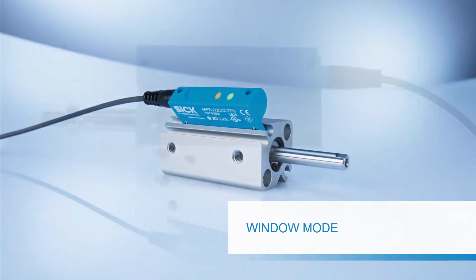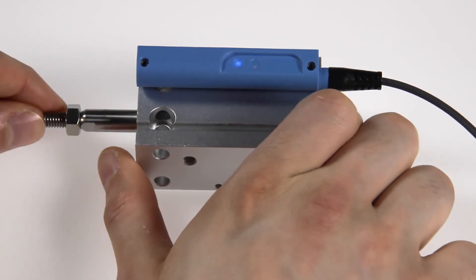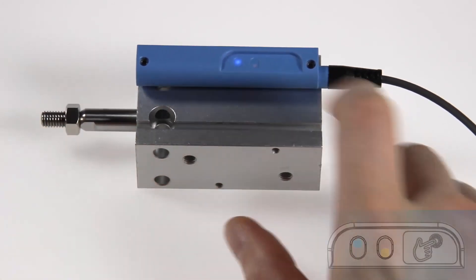Window mode. When using the window mode, a window between an upper and a lower threshold is defined. The switching output is active when the piston is located between the two thresholds. In order to set the first threshold, move the piston into the first position.